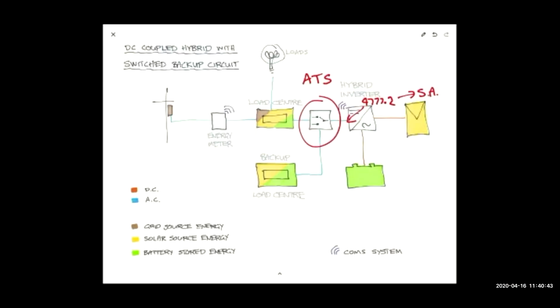This also applies to the CT that would trigger operation of the ATS. Since an ATS is a piece of electrical equipment, it needs to be suitable for its application, like a circuit breaker or any other equipment installed into an electrical system, which has test standards associated with it. It may fall under a requirement by the utility that it needs to be tested. When doing commercial systems with grid protection requirements, they may specify what products can be used or want to test them. So yes, there are definitely safety considerations around that.